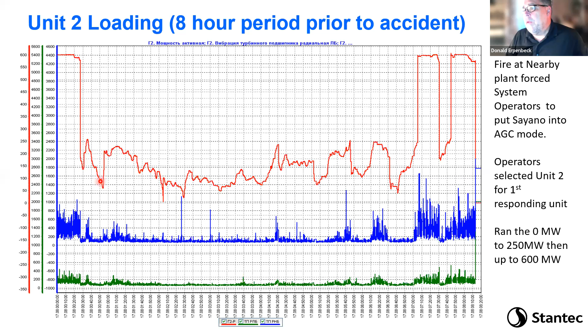Now, this is a very unusual operating regime for any hydropower turbine, and here's why. The blue here represents the efficiency curve of a typical Francis turbine. There's a rough zone in the middle, and it usually happens between about 40 and 60% power. This is what we call the part load rough zone. And this is not a little bit rough, it feels like an earthquake. If you're down in the powerhouse, every time they ramp up through that, which in this case would have been about 300 megawatts to about 450 or 500 megawatts, they would go through this rough zone.